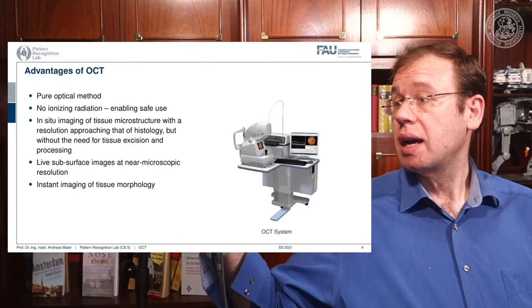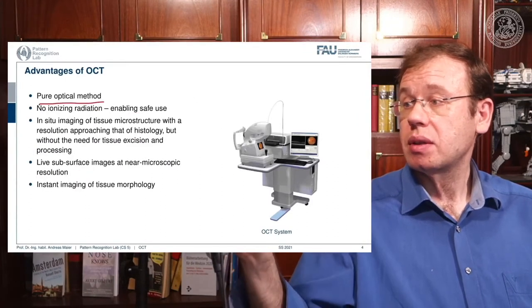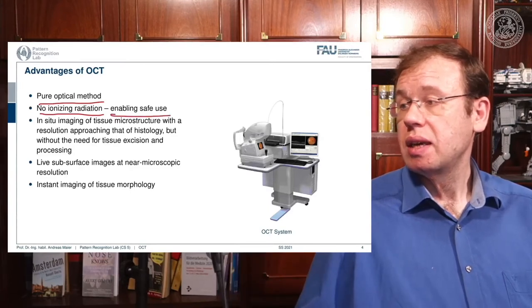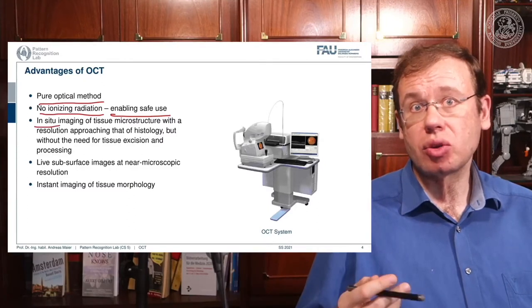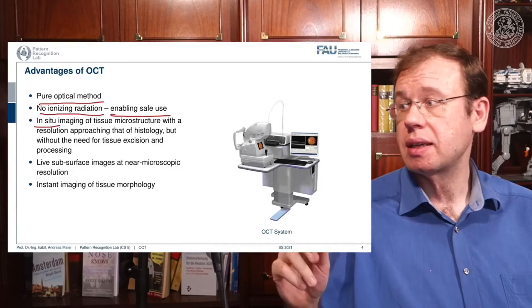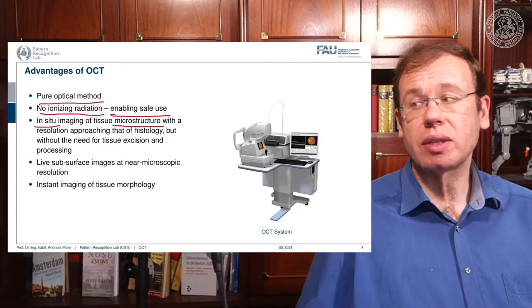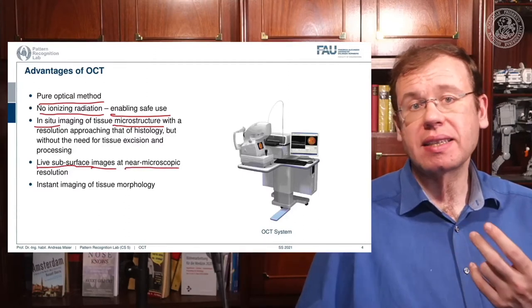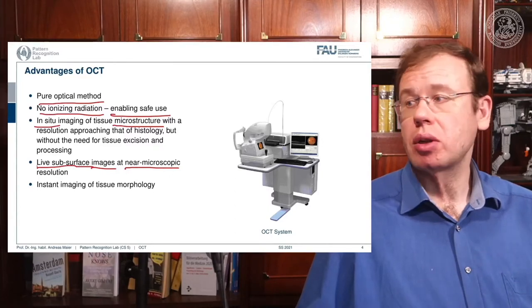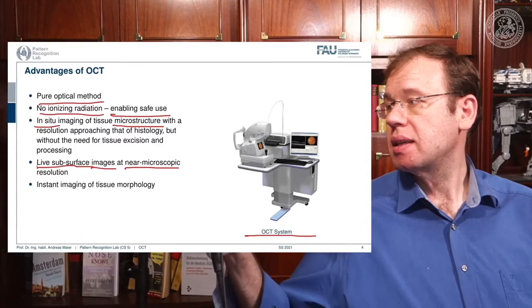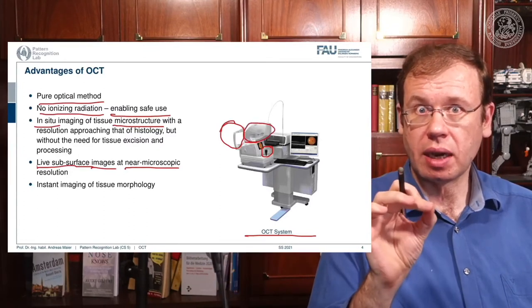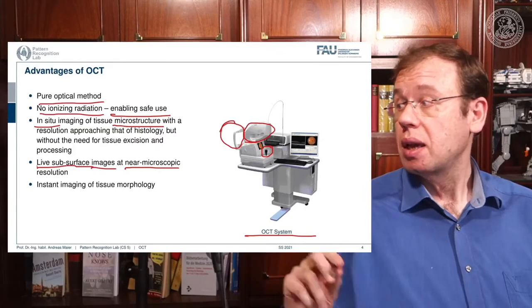The advantages of OCT: it's a pure optical method with no ionizing radiation — essentially all optical light — so it's safe for use. You do in-situ imaging, directly imaging the tissue without operating on the eye or extracting tissue. You get microstructure at very high resolution, live subsurface images at near-microscopic resolution, and instant imaging of tissue morphology. Here you see an OCT system where the patient positions their head and the operator aligns the imaging device with the optical axis of the eye.